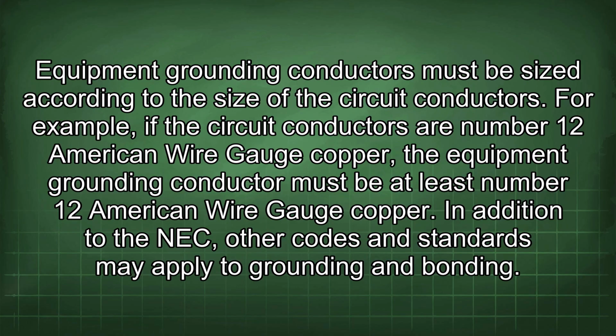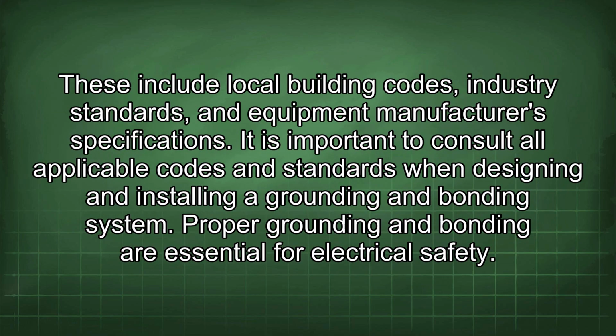Equipment grounding conductors must be sized according to the size of the circuit conductors. For example, if the circuit conductors are number 12 American wire gauge copper, the equipment grounding conductor must be at least number 12 American wire gauge copper. In addition to the NEC, other codes and standards may apply to grounding and bonding. These include local building codes, industry standards, and equipment manufacturer specifications. It is important to consult all applicable codes and standards when designing and installing a grounding and bonding system.